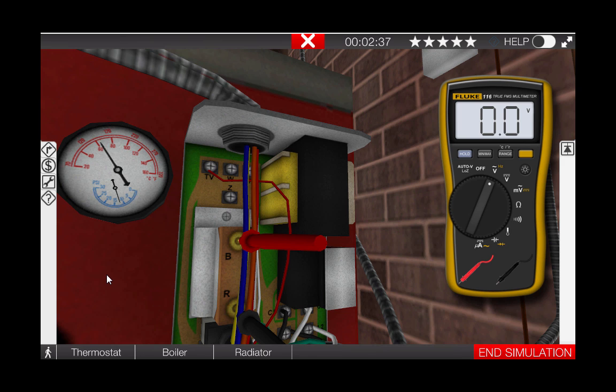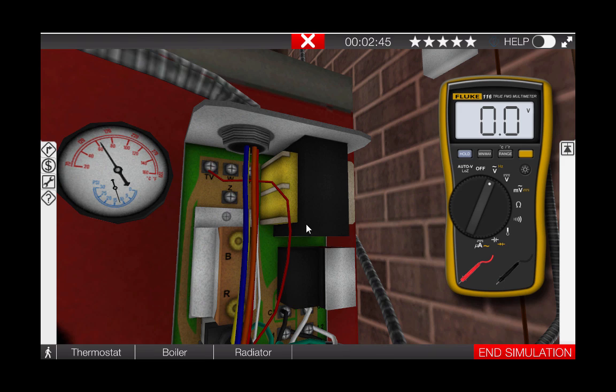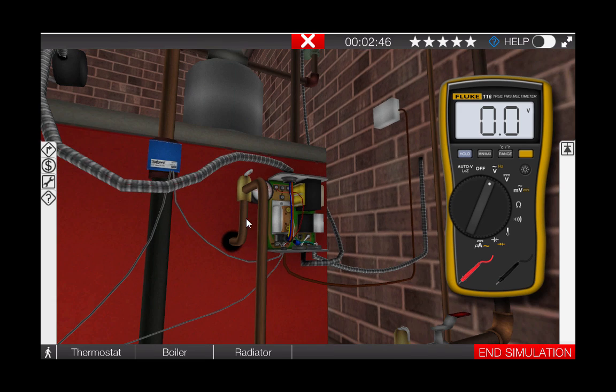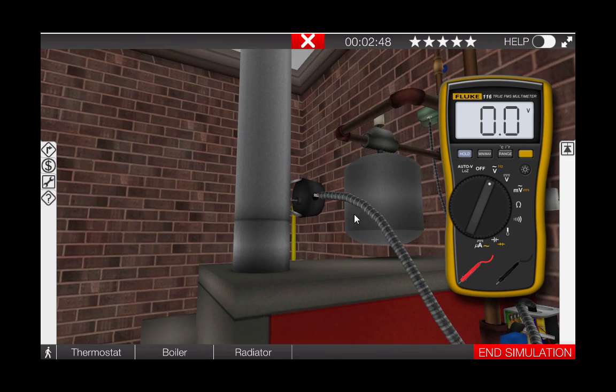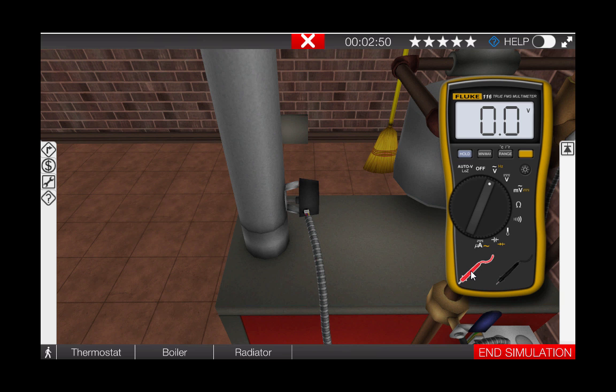Next we need to go and see if 24 volts is being sent to the motor of the vent damper. Begin by storing leads of the multimeter back at the multimeter by clicking on them. Next let's go up to the vent damper, right click to center and measure voltage at the motor connections.